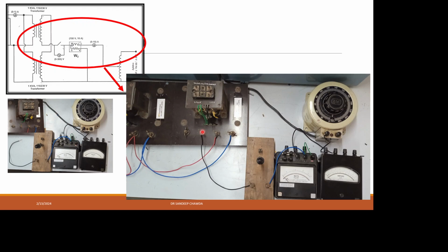Later, when checking, since these HV sides are connected in series phase opposition, you will need a voltmeter to verify this. We haven't connected a voltmeter across the switch yet, but you can connect one, or use a multimeter, to measure the voltage and confirm whether the transformers are properly connected in series phase opposition.